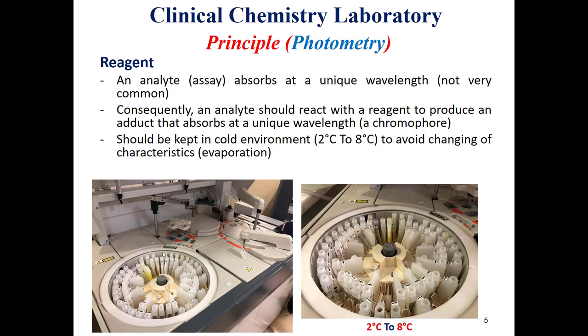This reagent — as we can see in this photo of the AU400 analyzer — comes in two types: reagent 1 and reagent 2. This reagent should be stored in the analyzer at a specific temperature ranging between 2 to 8 degrees. We should have a refrigerator in the analyzer to avoid changing the characteristics of the reagent and to increase their stability on board, which means inside the analyzer. This refrigeration is to avoid evaporation, so we need to store these reagents at 2 to 8 degrees to avoid evaporation and changes in reagent characteristics, which could lead to inaccuracy in the analyzer readings.